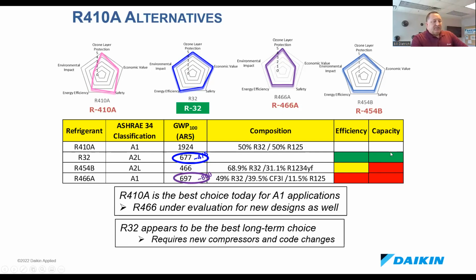When you look at the double greens, that's an advantage for the R32, but the disadvantage is you really have to redesign your compressors and your combination of compressors and heat exchangers to take full advantage of it. Whereas 454B, from a capacity standpoint, behaves more like 410A. So it may be easier to transition existing 410A designs to 454B designs simply by compressor and oil changes and everything else. But I think going forward, the R32 and the 454B will both be used quite a bit by different manufacturers in the same or even different applications. So that's one where it's going to be interesting to see how the market ends up playing out.